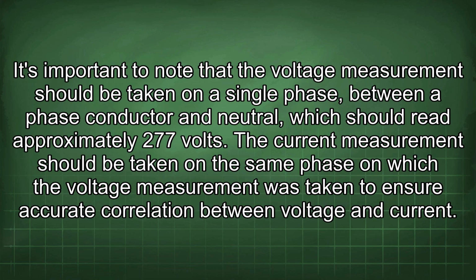It's important to note that the voltage measurement should be taken on a single phase between a phase conductor and neutral, which should read approximately 277 volts. The current measurement should be taken on the same phase on which the voltage measurement was taken to ensure accurate correlation between voltage and current.